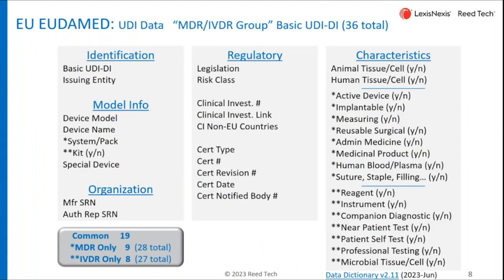We won't go into all the attributes connected to a Basic UDI-DI, but this is the list. They're grouped around some information about the model and some information about the organization — you should have received your Single Registration Number for your manufacturer by now. If you're non-European-based, you'll need an authorized representative, and that entity will also have an SRN. There are a number of fields about regulatory, and on the right-hand side you see a number of characteristics: the second grouping is appropriate for medical devices, and the third group at the bottom is for in vitro diagnostics. All those values would have to be the same for every device inside that medical device Basic UDI-DI.